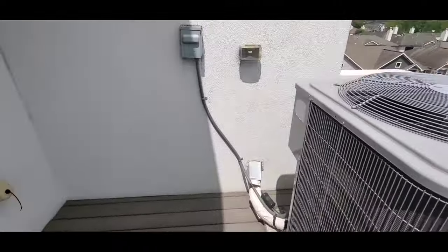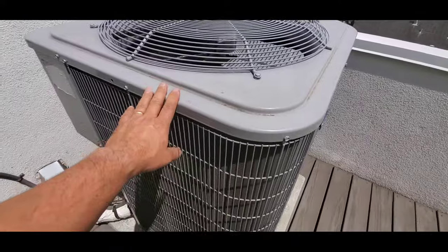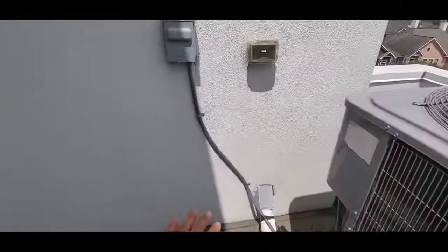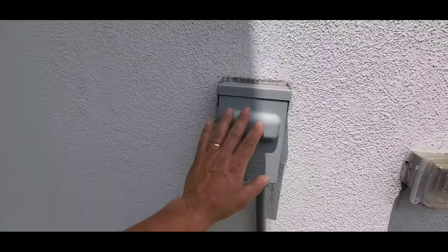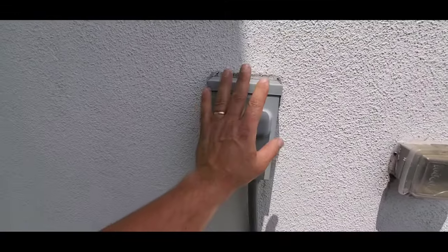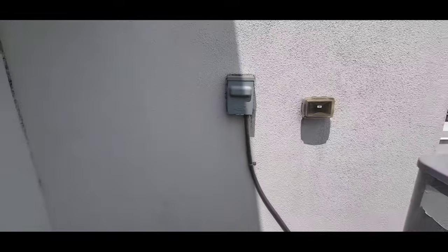This is required to be in sight of the condensing unit. So every condensing unit should have, within sight of that unit, a cutoff switch, and furthermore this disconnect switch requires working space in front of it.